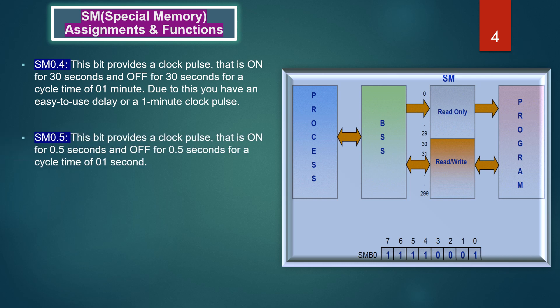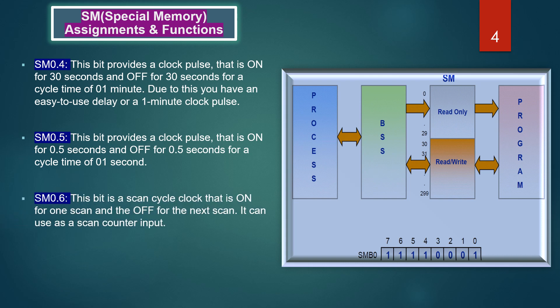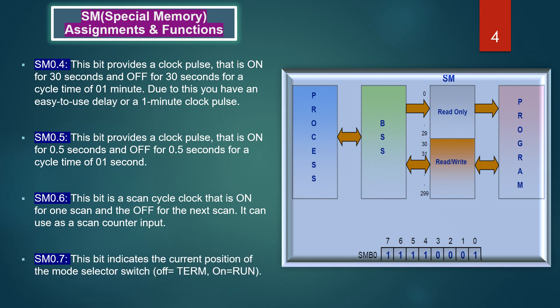SM 0.5: this bit provides a clock pulse that is on for 0.5 seconds and off for 0.5 seconds, for a cycle time of one second — an easy-to-use delay or one-second clock pulse. SM 0.4 and SM 0.5 have the same assignment and functions, just different timing. SM 0.6: this bit is a scan cycle clock that is on for one scan and off for the next scan; you can use it as a scan counter input.